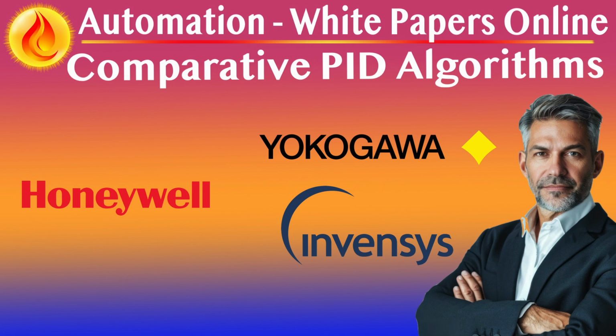Honeywell supports Type A, proportional on error, and Type C, proportional on PV, PID structures. This dual-mode design allows users to tailor setpoint response behavior explicitly. Type A produces a more aggressive setpoint response, suitable for inner loops or fast control, while Type C provides smoother setpoint tracking, ideal for outer loops or supervisory layers. These options offer consistent load response with customizable setpoint behavior, and tuning remains intuitive.